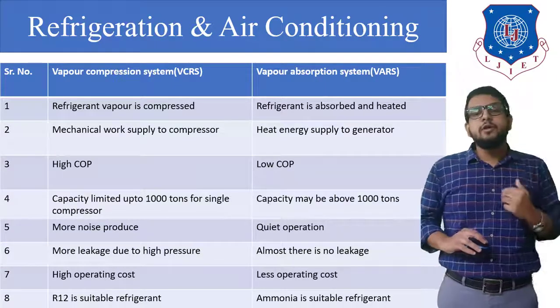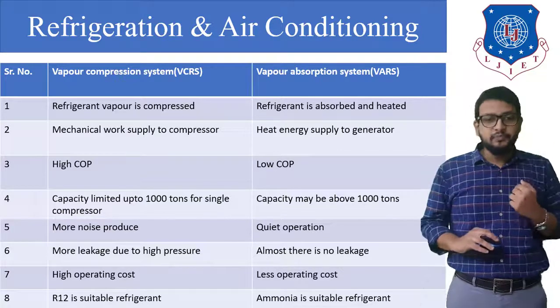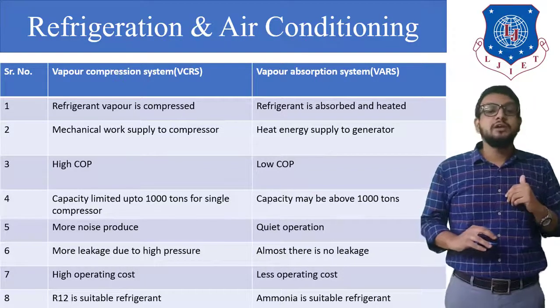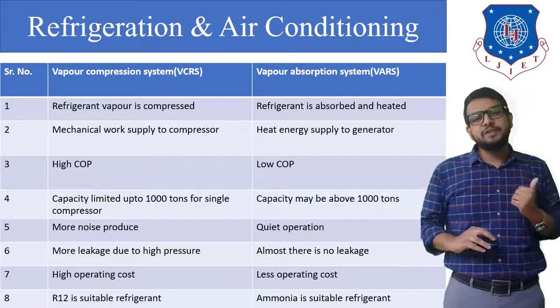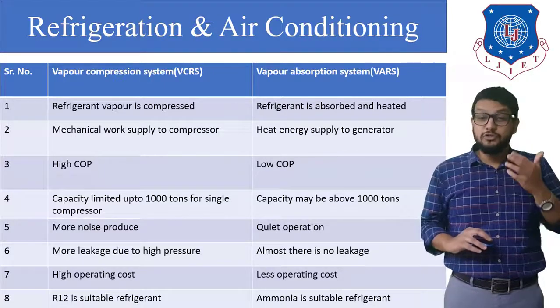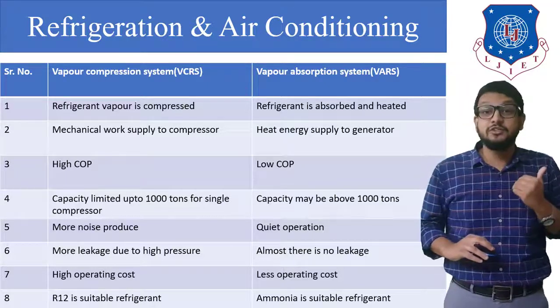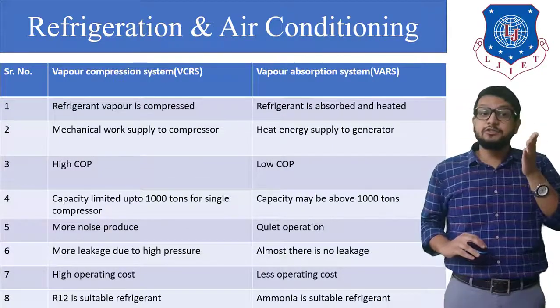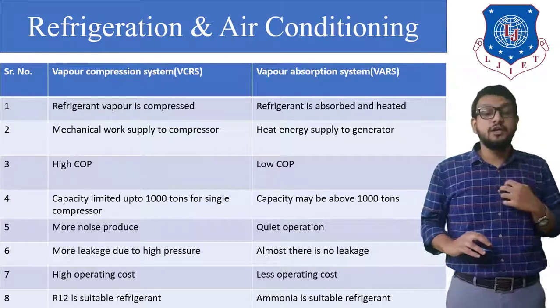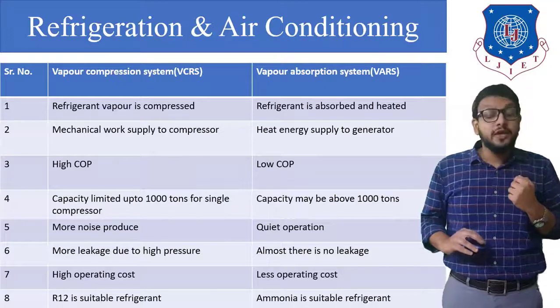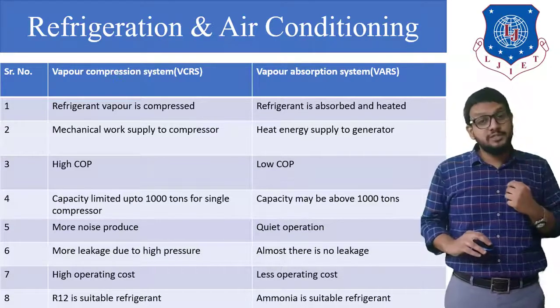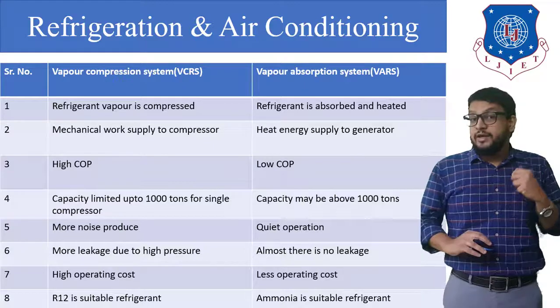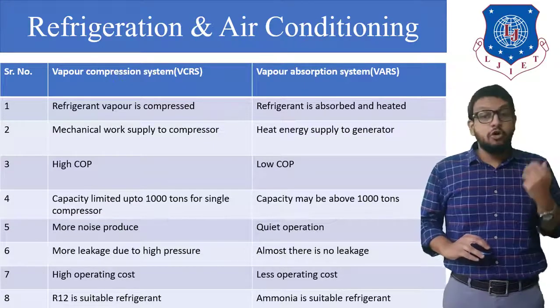Third, a high coefficient of performance (COP) can be obtained in the VCR system, whereas the COP is quite low in the VAR system. Fourth, the capacity of the VCR system is limited to around 1000 tons for a single compressor, whereas the VAR system capacity exceeds 1000 tons — so the VAR system is used in large ice manufacturing plants, while the VCR system is used for domestic purposes. Fifth, more noise is produced in the VCR system due to the reciprocating compressor's piston motion, whereas the VAR system using a generator operates quietly.